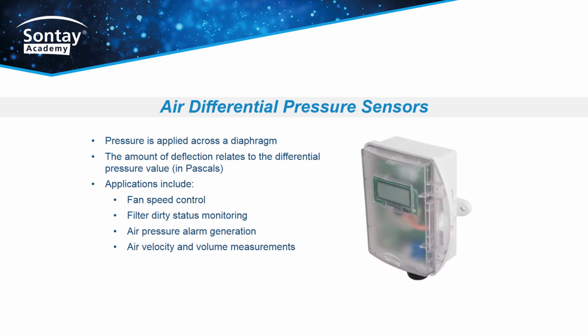Air differential pressure sensors. Pressure is applied across the diaphragm. The amount of deflection relates to the differential pressure value in pascals. Applications include fan speed control, filter dirty status monitoring, air pressure alarm generation, and air velocity and volume measurements.